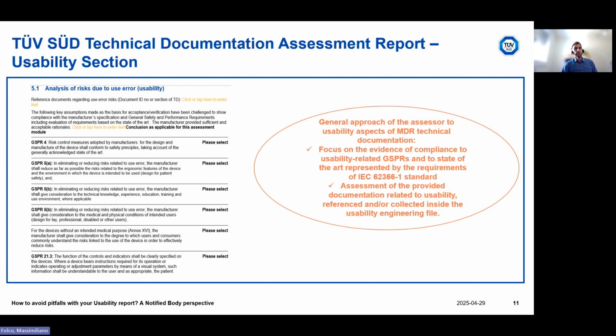Then the assessor has to also consider the state-of-the-art standards and the applicable requirements of the state-of-the-art standards. In this case, IEC 62366-1 is the main state-of-the-art standard applicable for usability. Even if in this report we do not specifically have the requirements of the standard to be checked with a checkbox, we are required to do that, so to consider also those requirements for understanding if the technical documentation fulfills or not those requirements, and to raise deficiencies in case any gap or inconsistency is observed.